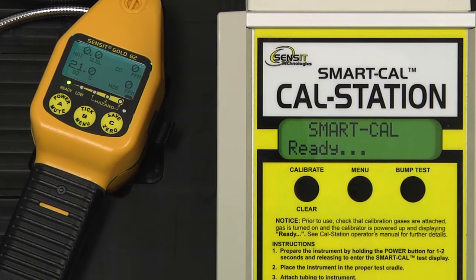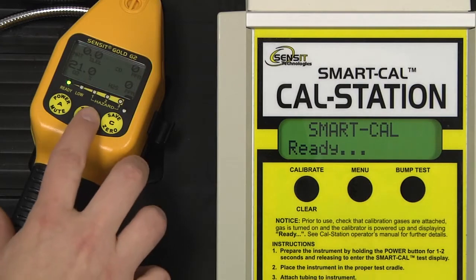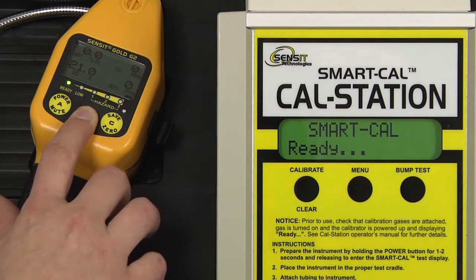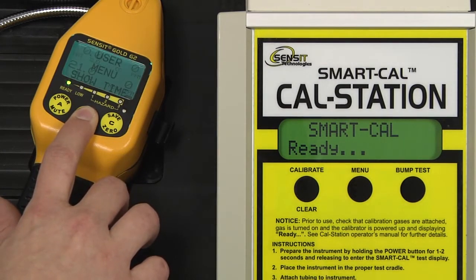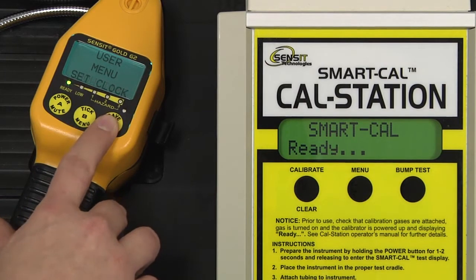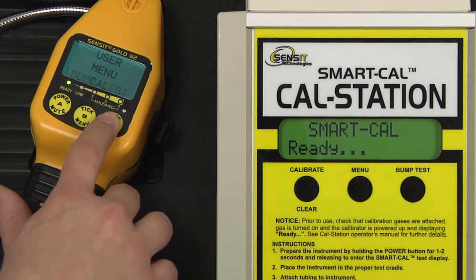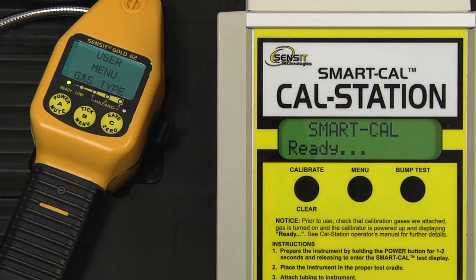The cal station cannot automatically calibrate for both methane and propane. And if we would like to change which gas it's calibrating to, we need to change the gas type in the instrument to reflect that. To do so, enter into the user menu by pressing and holding the B button, and scroll through this menu by pressing and releasing the C button until gas type appears.